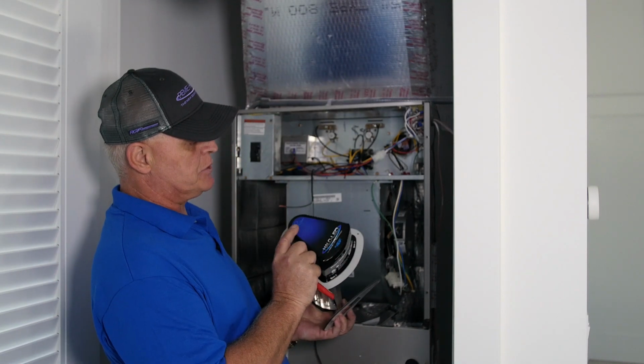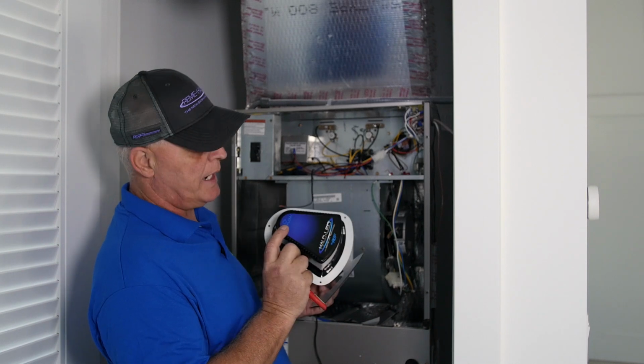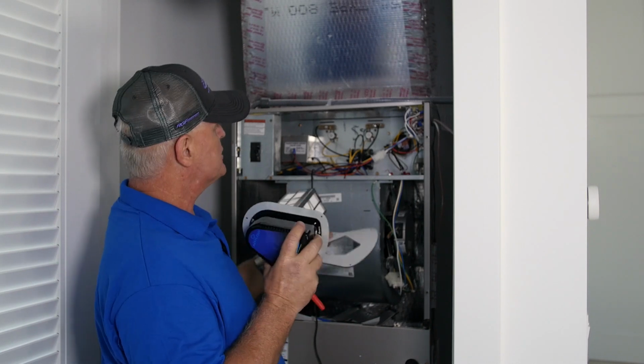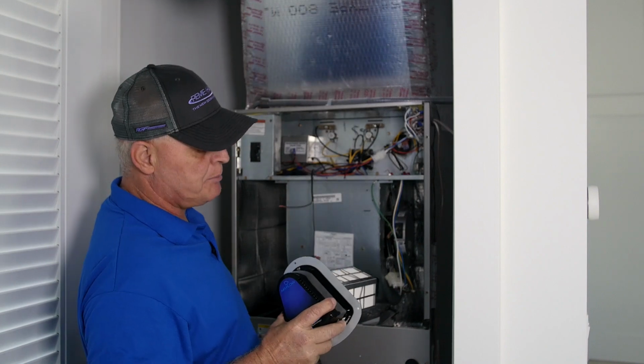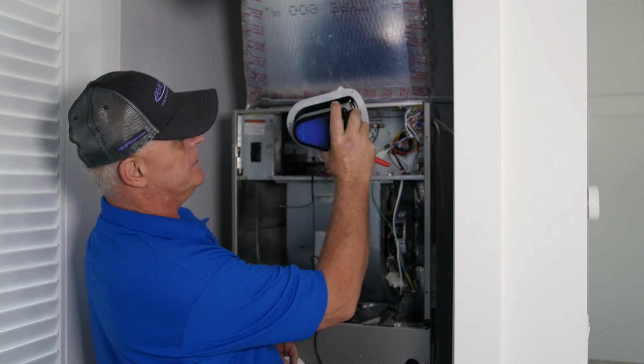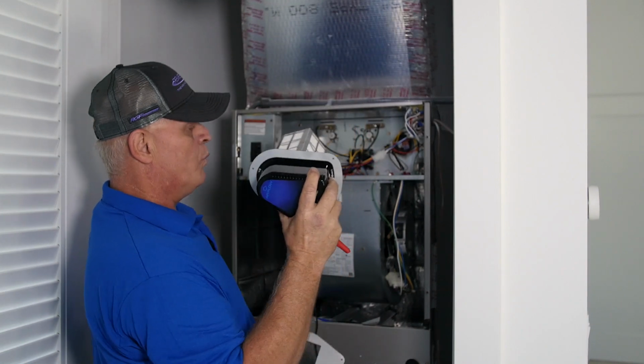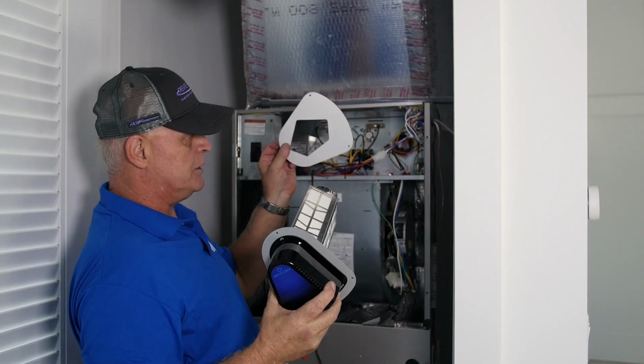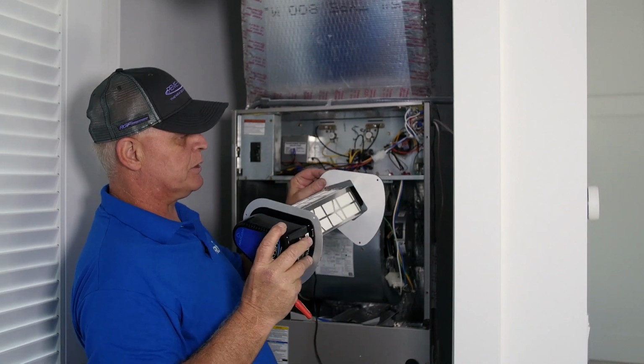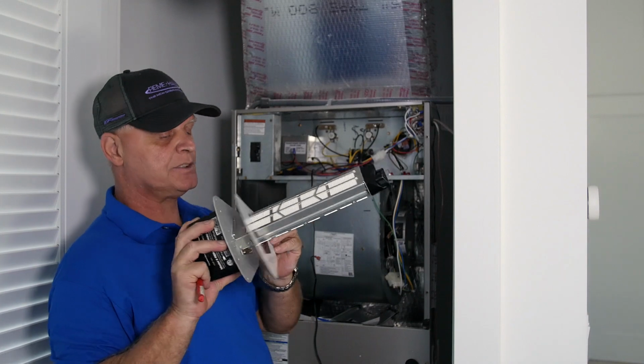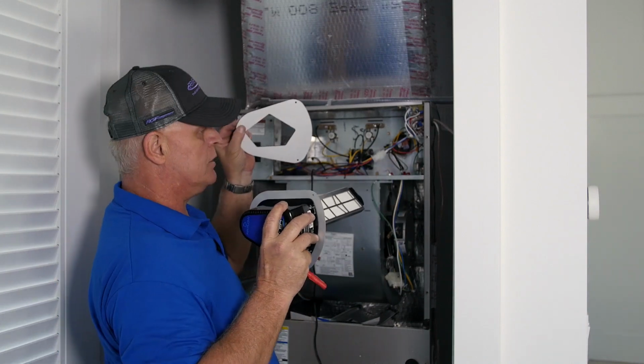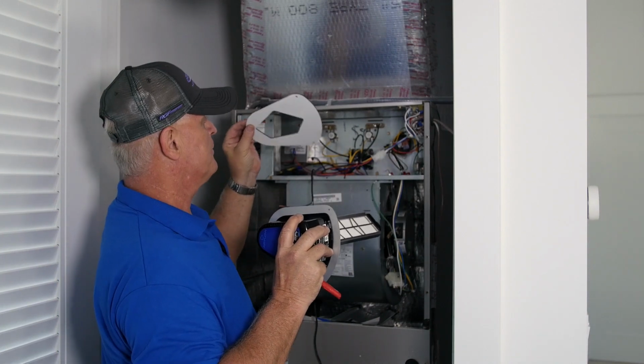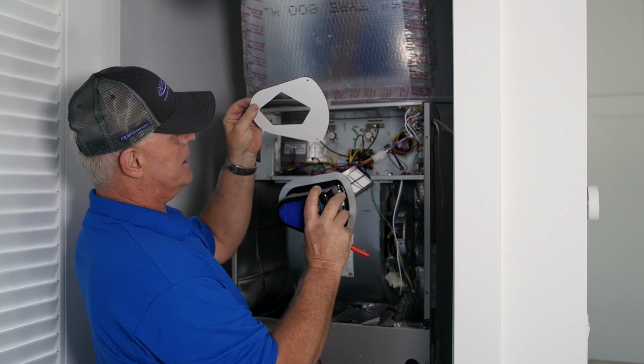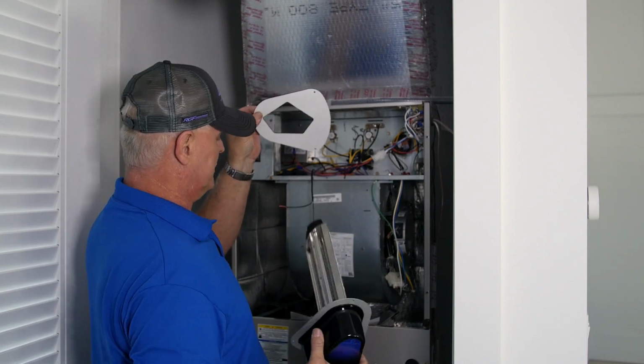So you need to pay particular attention to the airflow arrow on the unit. In this particular unit, airflow is up, so we're going to be installing it in this orientation. When you're installing it, you're going to be using your gasket. Be particularly careful when you put your gasket on as to which direction it goes. It is directional. So in this instance, our gasket is going to mount in this direction.